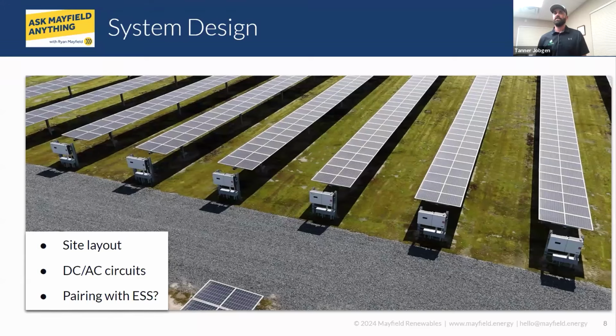And we have done central inverters as well with DC combiners throughout the field. Really the central inverter, if there is any advantage, it would be just there's less equipment. So you bypass the need for a switchgear. Typically, the central inverter is coupled to the step-up transformer. So there's been some cost savings with that, but at the system size that we're typically working in, that minimal savings is probably irrelevant to the long-term performance of the site if you ever had one instance of a failure.